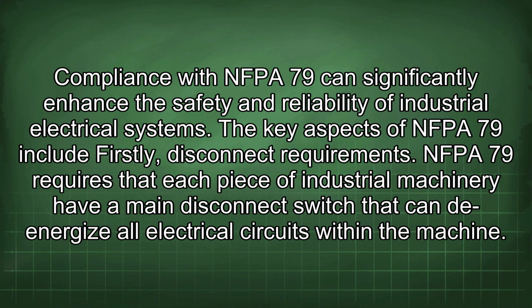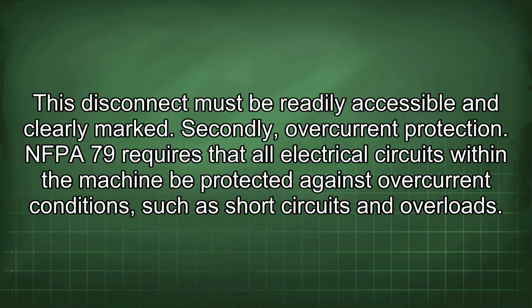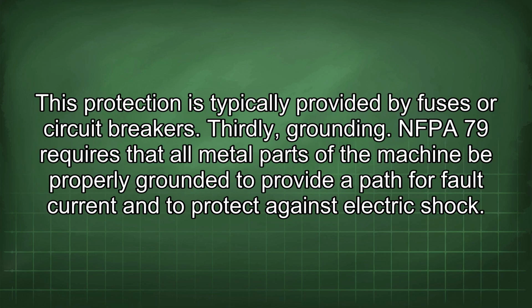The key aspects of NFPA 79 include: firstly, disconnect requirements. NFPA 79 requires that each piece of industrial machinery have a main disconnect switch that can de-energize all electrical circuits within the machine. This disconnect must be readily accessible and clearly marked. Secondly, overcurrent protection. NFPA 79 requires that all electrical circuits within the machine be protected against overcurrent conditions such as short circuits and overloads. This protection is typically provided by fuses or circuit breakers. Thirdly, grounding. NFPA 79 requires that all metal parts of the machine be properly grounded to provide a path for fault current and to protect against electric shock.